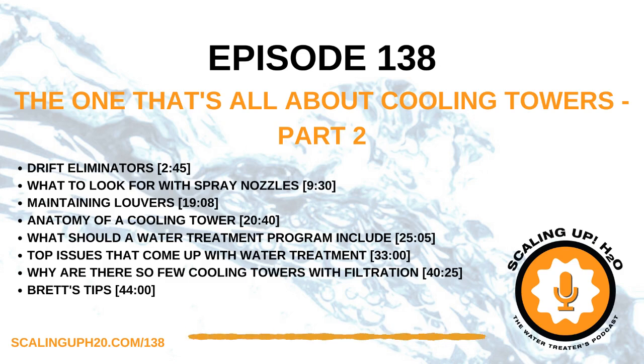To reiterate that point, in crossflow you've got the air coming in on two sides and going across the falling water, so they're moving perpendicular to each other. Now all the water has to do is turn 90 degrees to get in the airstream, those water droplets. So it's easier to turn and get up in the airstream. So you'll see a little bit higher drift rates in crossflow towers compared to counterflow towers.